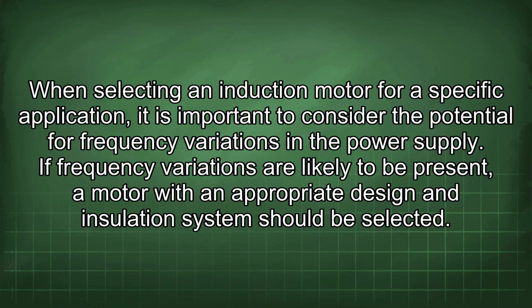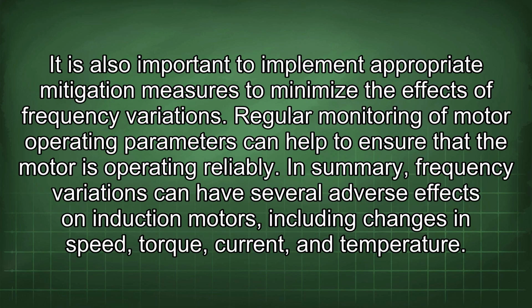If frequency variations are likely to be present, a motor with an appropriate design and insulation system should be selected. It is also important to implement appropriate mitigation measures to minimize the effects of frequency variations. Regular monitoring of motor operating parameters can help to ensure that the motor is operating reliably.